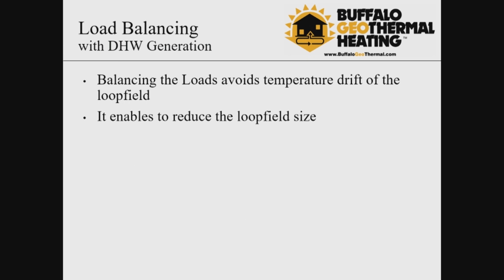And the other challenge, balancing the loads on this building, especially with the restaurant in there. Even in Buffalo, New York, a multifamily building is cooling dominated, meaning the heat that we reject into the ground during the AC season outweighs the heat we need to heat the building in the winter. If this is not counteracted, as we saw in the previous graphs, we experience a temperature drift.